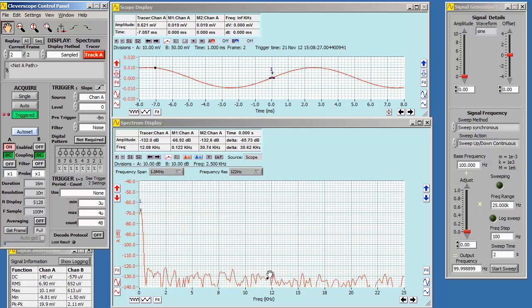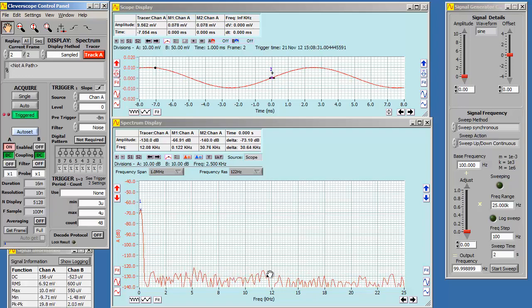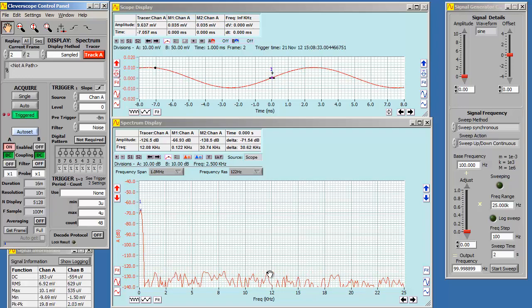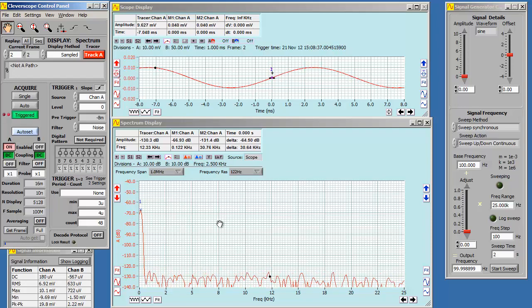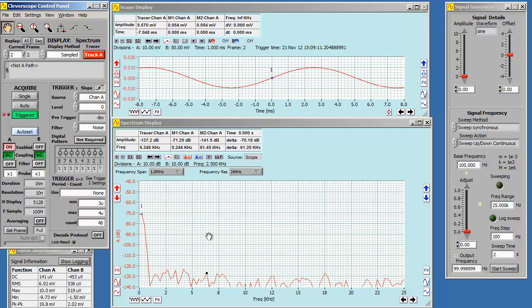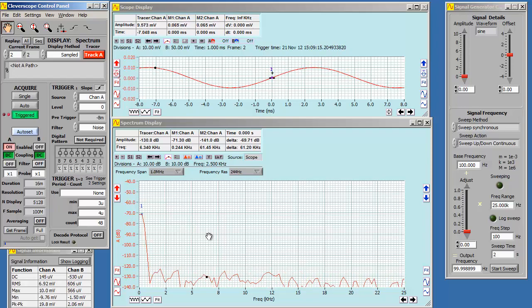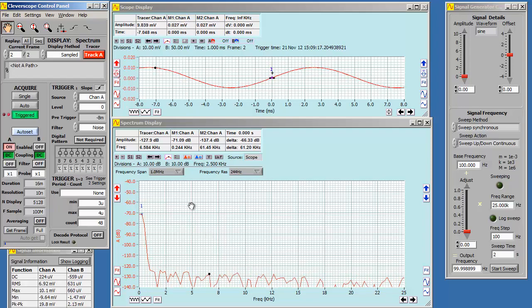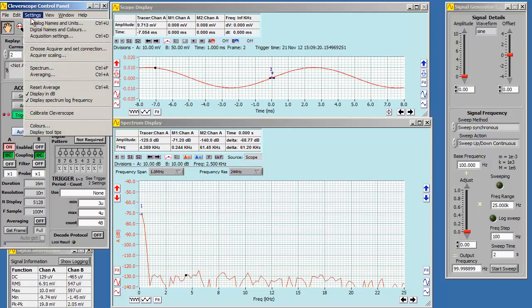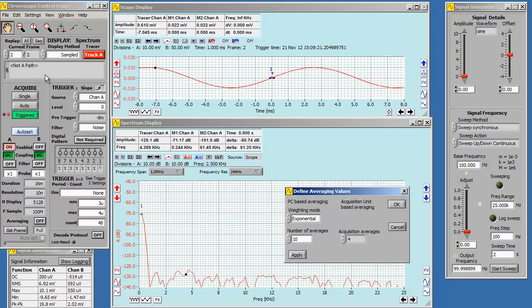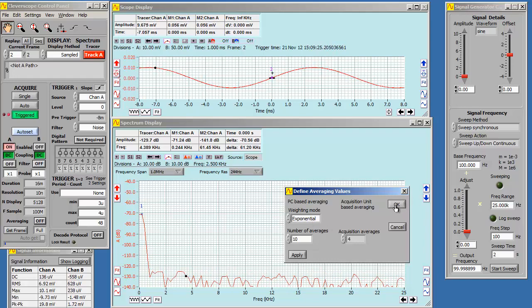A further way to improve the noise is to use averaging. You can use averaging either in the time domain using triggered capture or in the frequency domain using auto capture. Time averaging gives the greatest noise reduction for a reliably triggered signal. We use the settings averaging menu. We see exponential weighting, which is good, and 10 averages, also good.